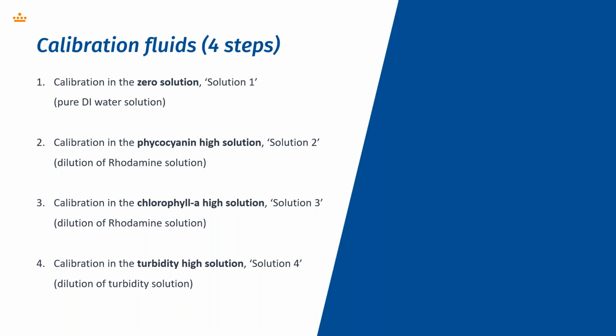The second one is calibration in the phycocyanin high solution, called solution 2, and that's a dilution of a rhodamine WT solution. The third step is the calibration in the chlorophyll A high solution, called solution 3, and that's a dilution of rhodamine solution. And then the last step, the fourth one, is the calibration in the turbidity high solution, called solution 4, and that's a dilution of the turbidity solution.